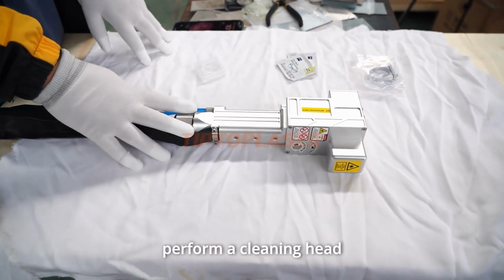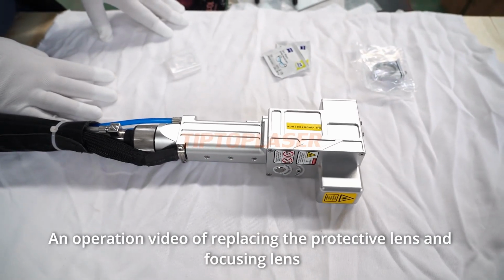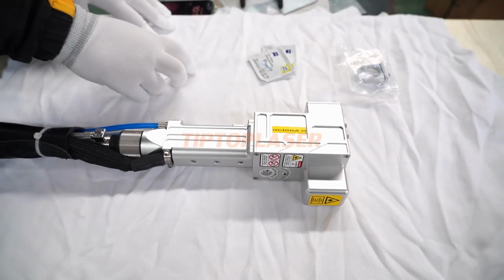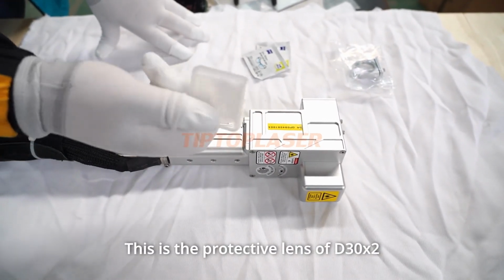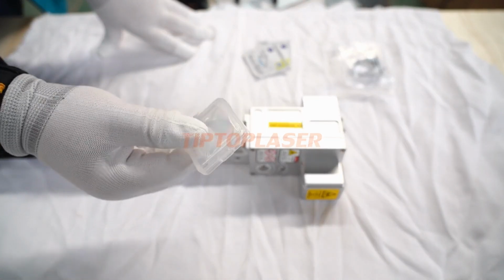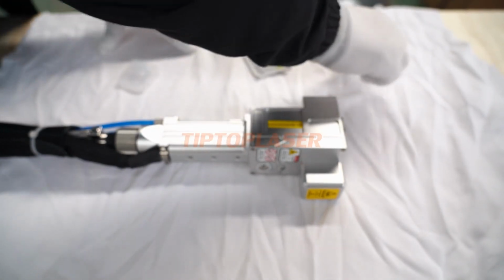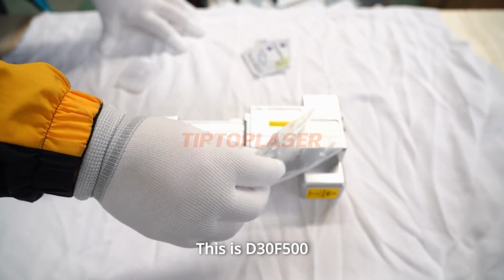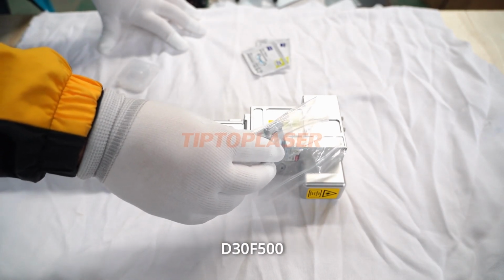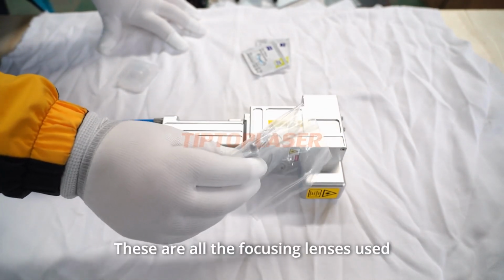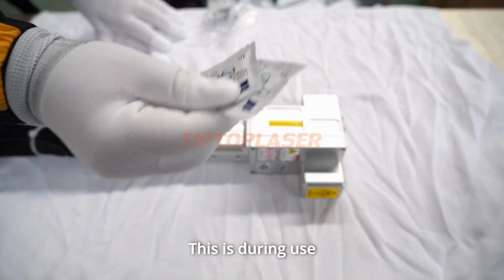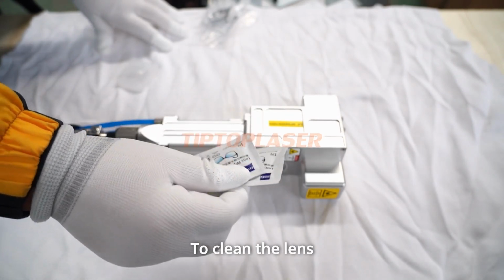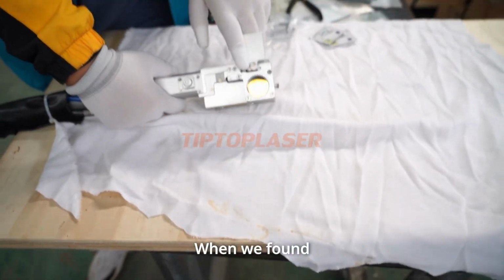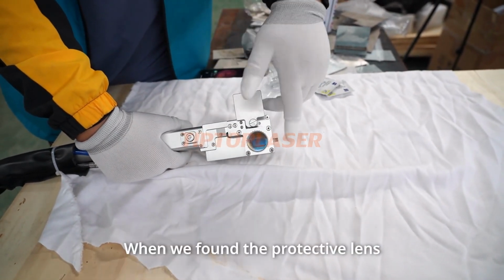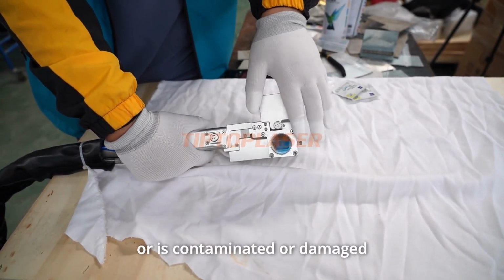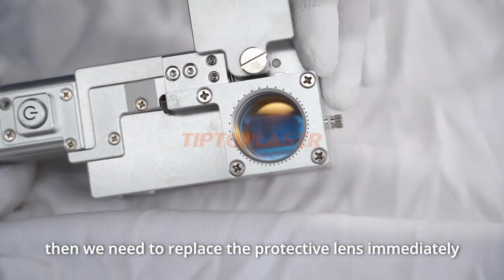Next, we perform an operation video of the cleaning head, replacing the protective lens and focusing lens. This is the protective lens of D30X2. This is D30F500. There are others. This is the focusing lens. These are all the focusing lenses used. During use, avoid dust from falling in. To clean the lens, use alcohol wipes. When we find the protective lens has a small black dot in the middle, or is contaminated or damaged, then we need to replace the protective lens immediately.